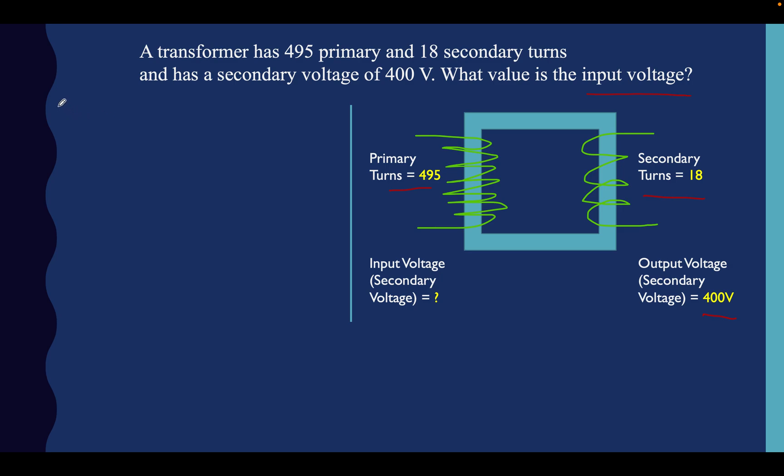This is the formula you're going to want to use for this. Input voltage is equal to the output voltage multiplied by the turns on the primary side divided by the turns on the secondary side. So we're going to divide the turns on the primary by the turns on the secondary, which is that number and that number, and we're going to multiply it by the output voltage.